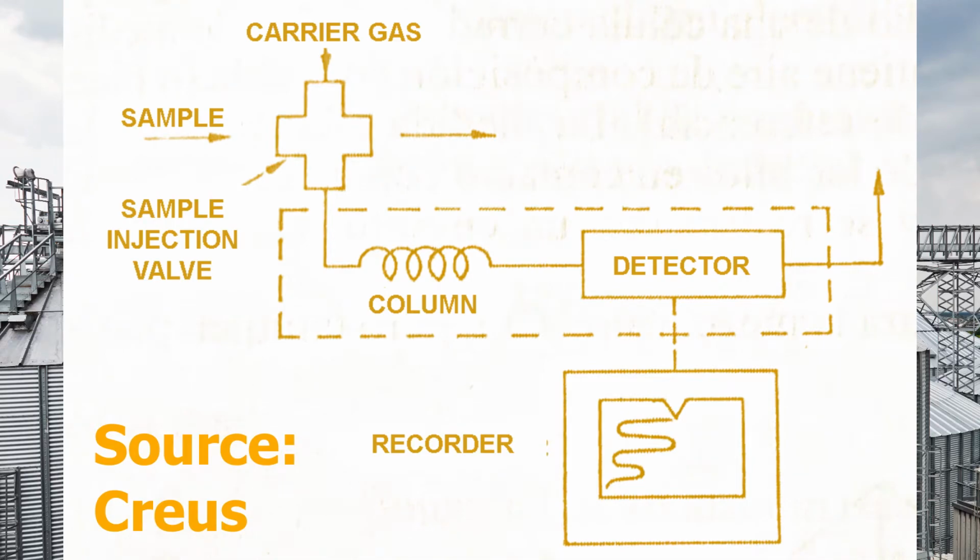Another complete apparatus that works on the principle of thermal conductivity is the chromatograph, which allows the components of a gas sample to be determined in a few minutes. It consists of a separation column for the gas components, a sampler, a controlled temperature chamber enclosing the detector, and a recorder that marks the peaks corresponding to the components on the graph.